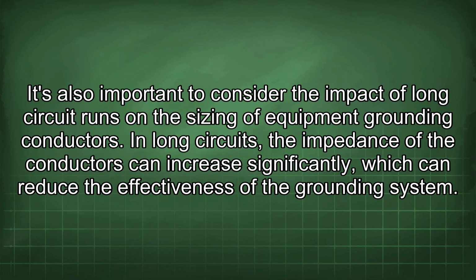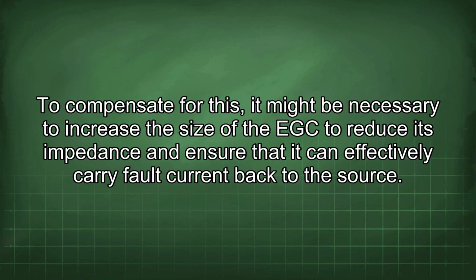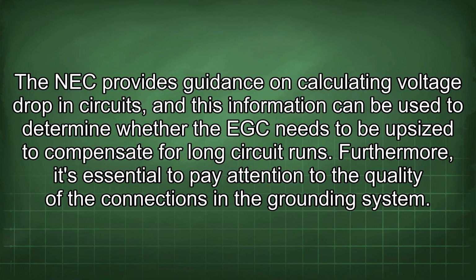It's also important to consider the impact of long circuit runs on the sizing of equipment grounding conductors. In long circuits, the impedance of the conductors can increase significantly, which can reduce the effectiveness of the grounding system. To compensate for this, it might be necessary to increase the size of the EGC to reduce its impedance and ensure that it can effectively carry fault current back to the source. The NEC provides guidance on calculating voltage drop in circuits, and this information can be used to determine whether the EGC needs to be upsized to compensate for long circuit runs.